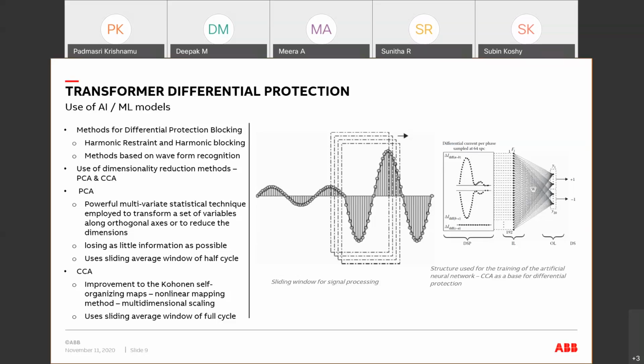Another widely used method is the harmonic current restraint or blocking. Most modern power transformer differential protection has harmonic restraint or blocking. The presence of second harmonic and fifth harmonic blocks the differential element of the protection. So the differential relay self-desensitizes during inrush currents, but the relay can still detect short circuit currents. To do this, the relay distinguishes between the inrush current and the short circuit current by the difference in the current's wave shape. So basically, you are looking at either waveform recognition or value recognition.